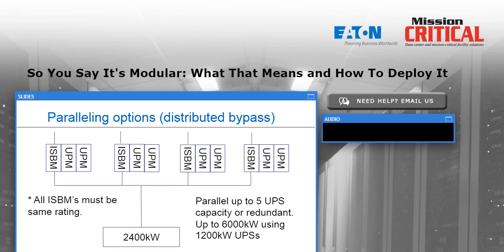It's because they have separate tie cabinets in a mirror image configuration, and there's no way that a problem in one system, or the A system, for example, could affect the B system. So that's one of those situations that if I want to take ultimate advantage of my dual power cord servers and a literal 2N UPS system, I can still use modular redundant systems on each side, but I would not be tying them together at a single point there.